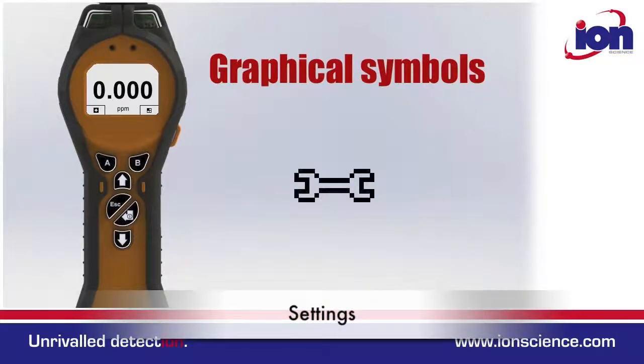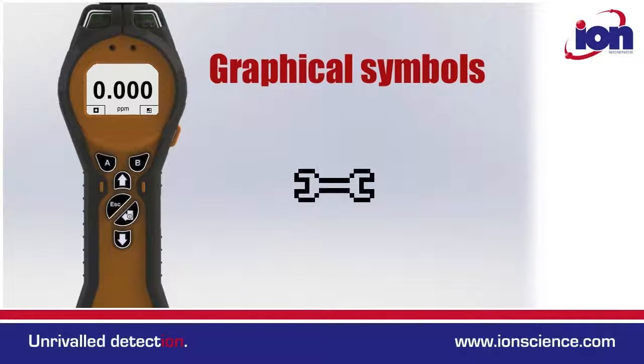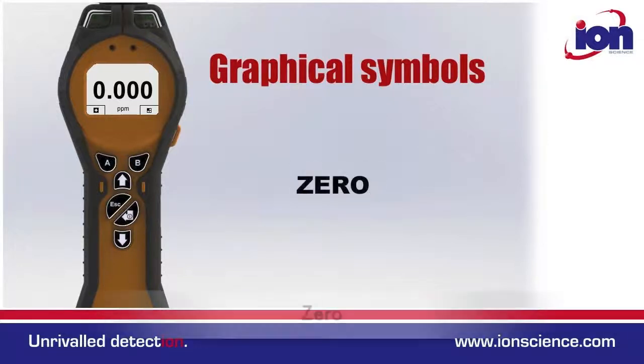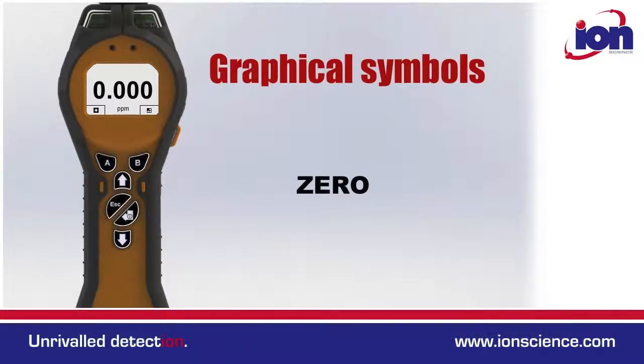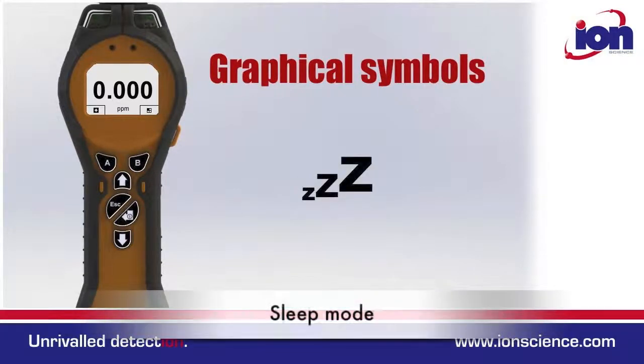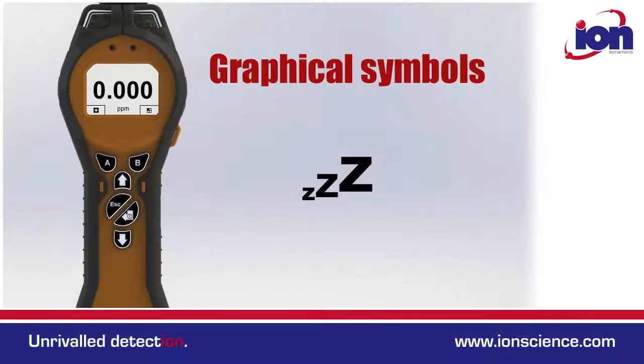Settings: this is where you adjust everything from backlight settings to a custom calibration. Zero: this allows you to zero out a known harmless background or use a fixed zero calibration point. Sleep mode: this puts the Tiger on standby, which conserves energy and avoids the full startup sequence.